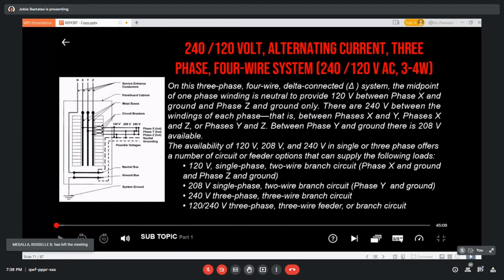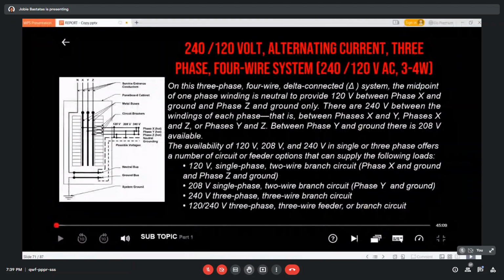The availability of 120 volts, 208 volts, and 240 volts in single or three-phase offers a number of circuit or feeder options that can supply the following loads. 120 volt single-phase two-wire branch circuit, phase X and ground, and phase Z and ground. 208 volt single-phase two-wire branch circuit, phase Y and ground. 240 volt three-phase three-wire branch circuit. 120/240 volts three-phase three-wire feeder or branch circuit. That's all, and thank you.